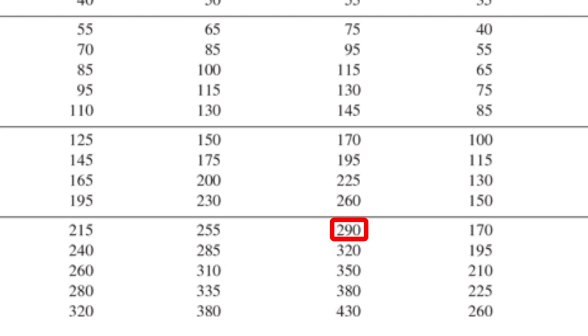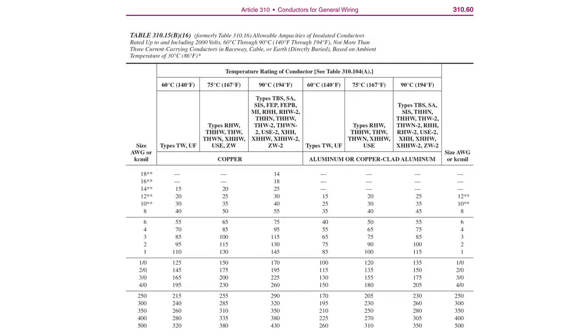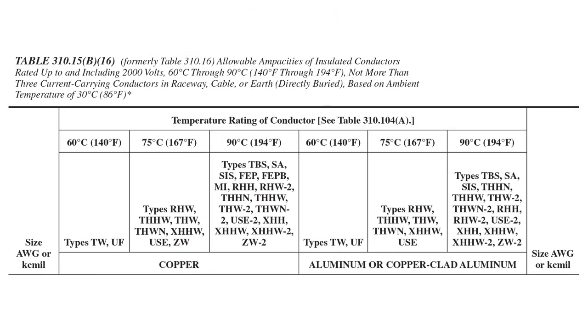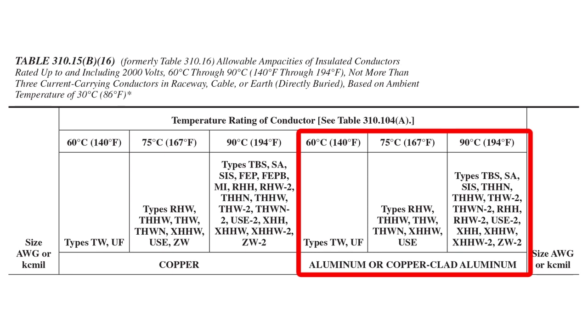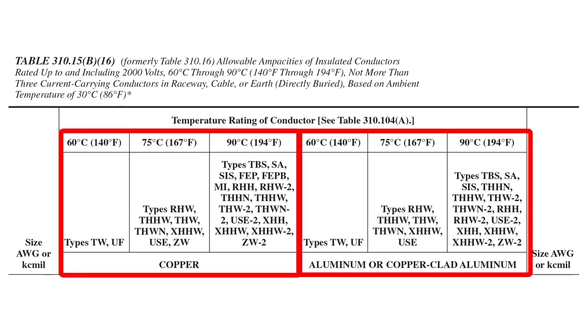And again, when you point to this particular table, Table 310.15(B)(16), there are rows and columns, and there are different ones. What are some of the common mistakes people make? They don't look it through, they don't read it thoroughly. They don't look through the right columns. There's one set for aluminum conductors, one set for copper conductors. There are different temperature ratings of the insulation. There's the type of insulation that's used, so you need to look at the whole thing.